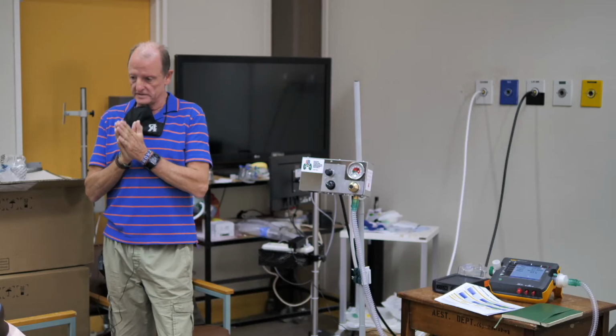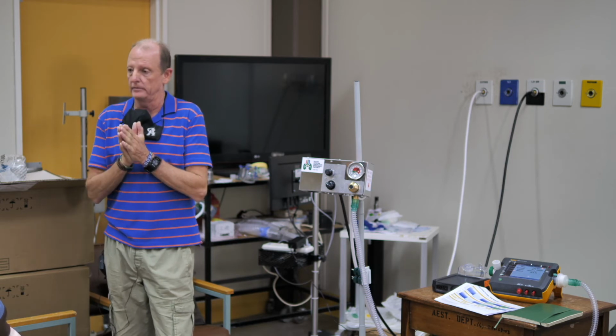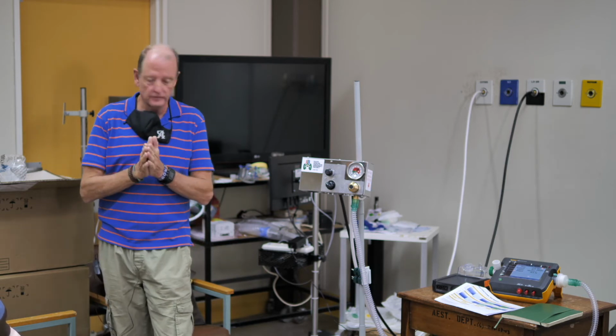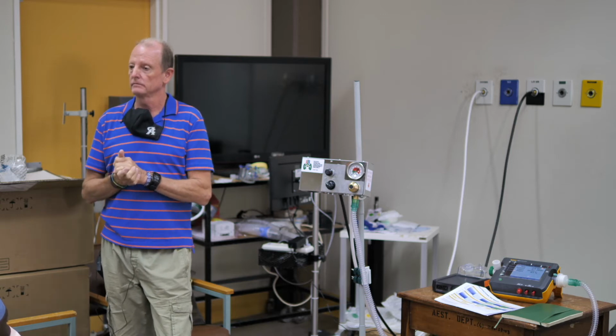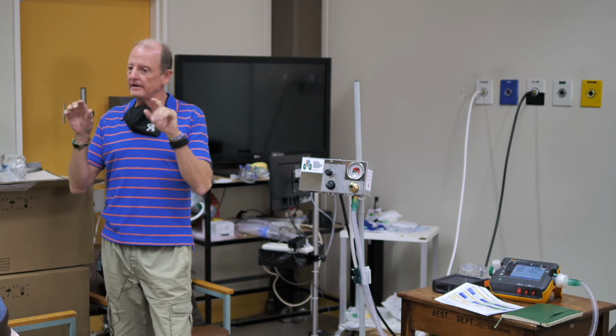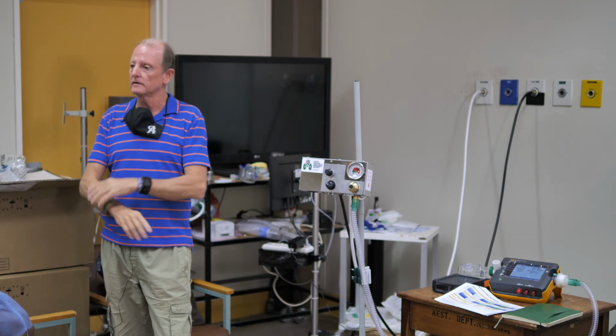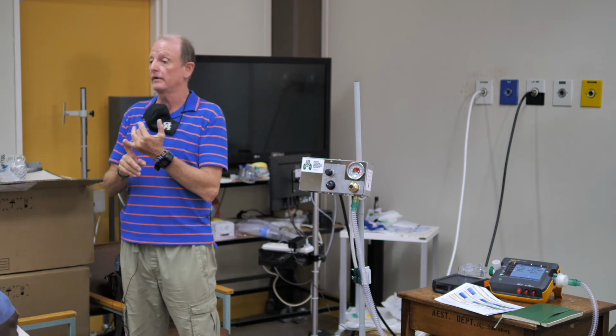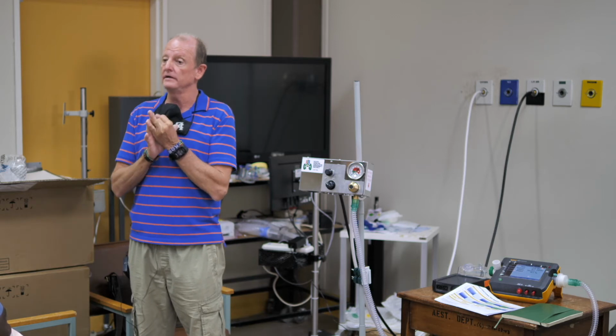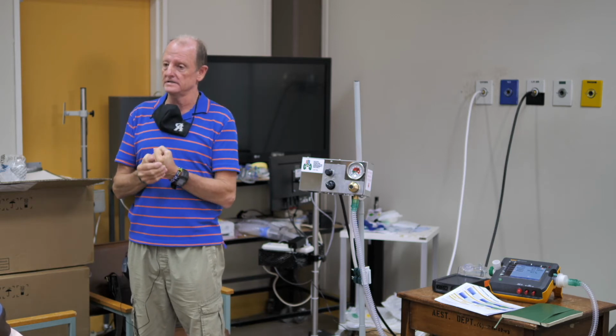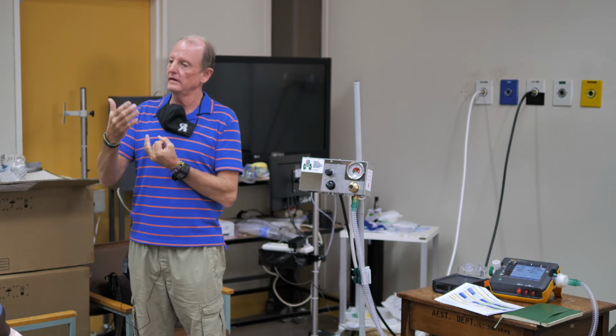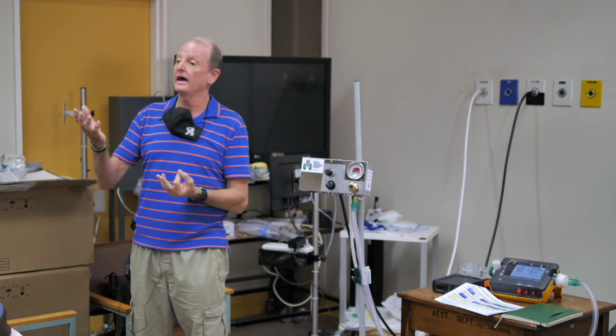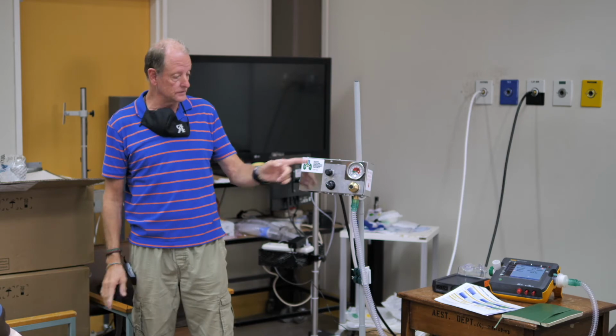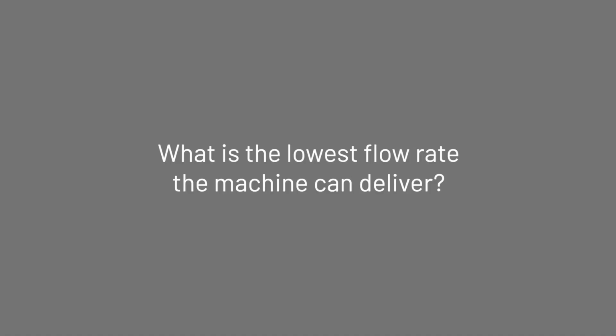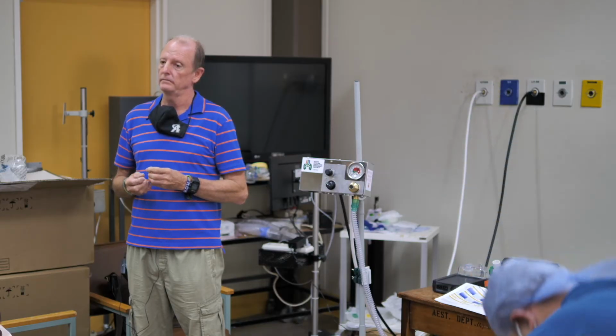Have you got test analyzers at the present moment that can do, for example, flow rates? I don't know. Have you got any ventilator test units that will give you a flow, because you need to do a flow rate from 20 liters to 60 liters. So if you've got any analyzer that can register that flow rate, and even a handheld oxygen analyzer to test that, 20 liters. Yeah, yeah.